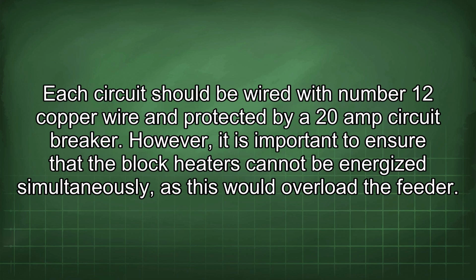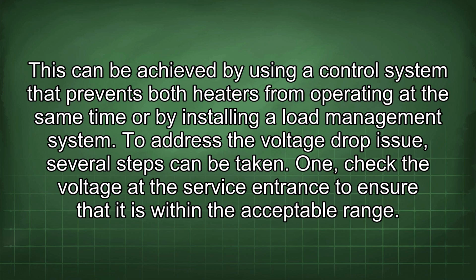However, it is important to ensure that the block heaters cannot be energized simultaneously, as this would overload the feeder. This can be achieved by using a control system that prevents both heaters from operating at the same time, or by installing a load management system. To address the voltage drop issue, several steps can be taken.